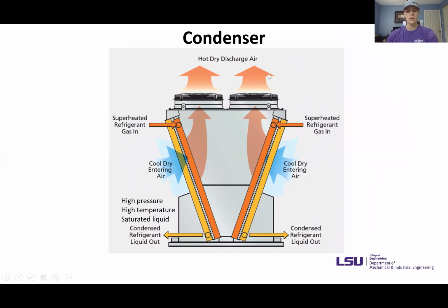Next, we're going to look at the condenser. So as the refrigerant enters as a superheated refrigerant into the condenser coils, it's going to run along horizontal copper pipes that are laid out in orange right here. And as the refrigerant flows through these coils, the fans are going to pull cool air from the environment over the coils and disperse the hot air taken from the refrigerant back into the environment. And as the refrigerant exits the condenser, it exits as a high pressure, high temperature, saturated liquid.